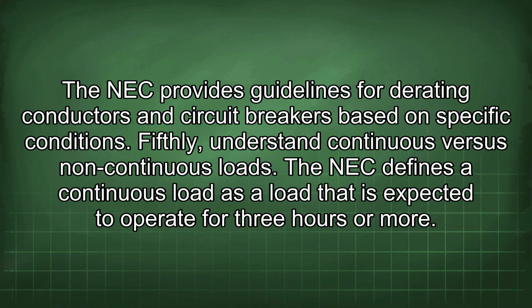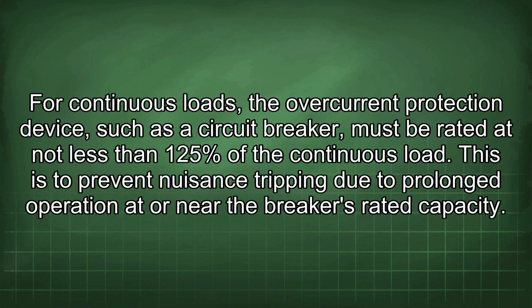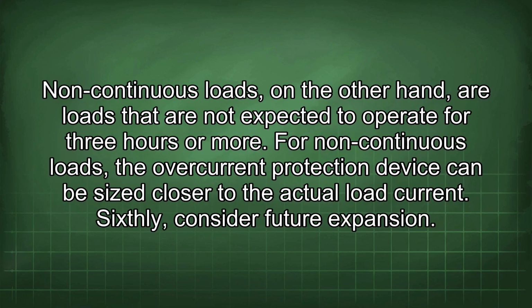Fifthly, understand continuous versus non-continuous loads. The NEC defines a continuous load as a load that is expected to operate for 3 hours or more. For continuous loads, the overcurrent protection device, such as a circuit breaker, must be rated at not less than 125% of the continuous load. This is to prevent nuisance tripping due to prolonged operation at or near the breaker's rated capacity. Non-continuous loads, on the other hand, are loads that are not expected to operate for 3 hours or more. For non-continuous loads, the overcurrent protection device can be sized closer to the actual load current.